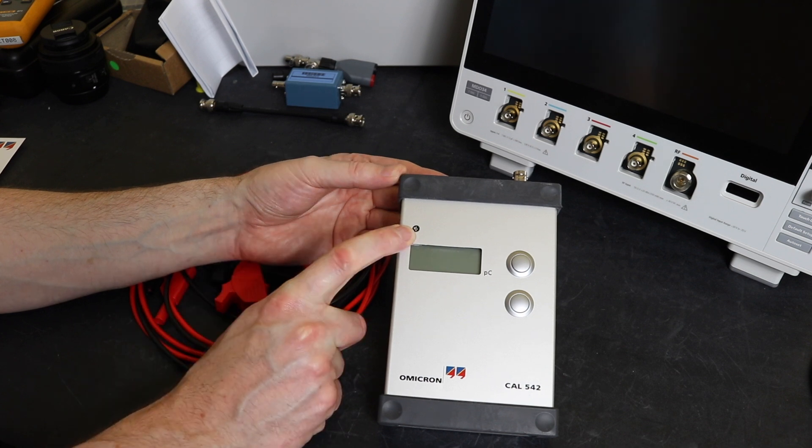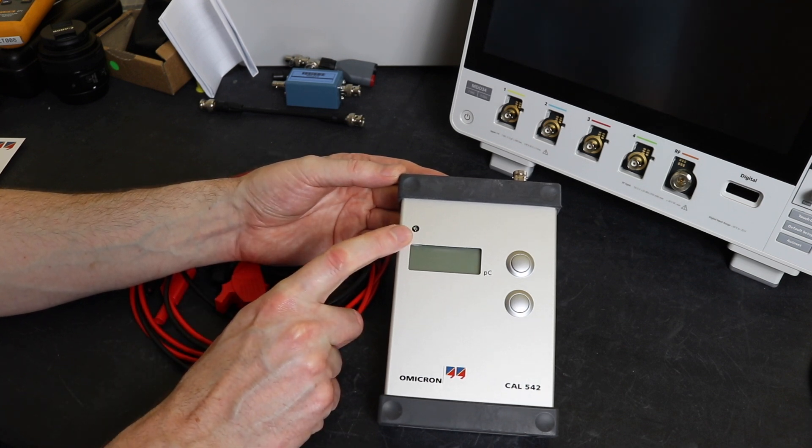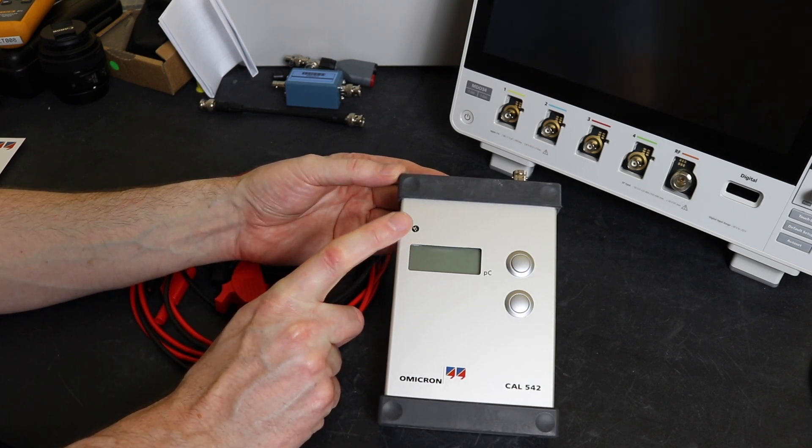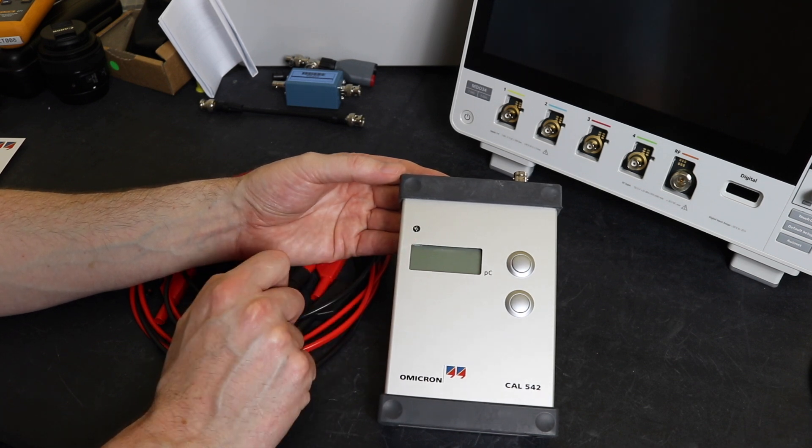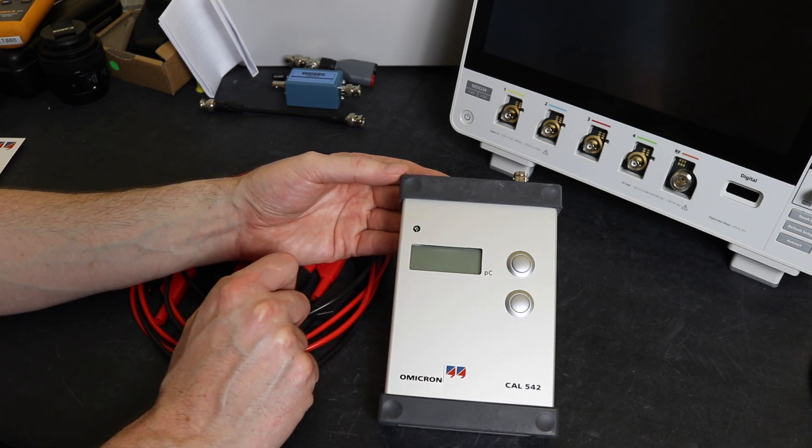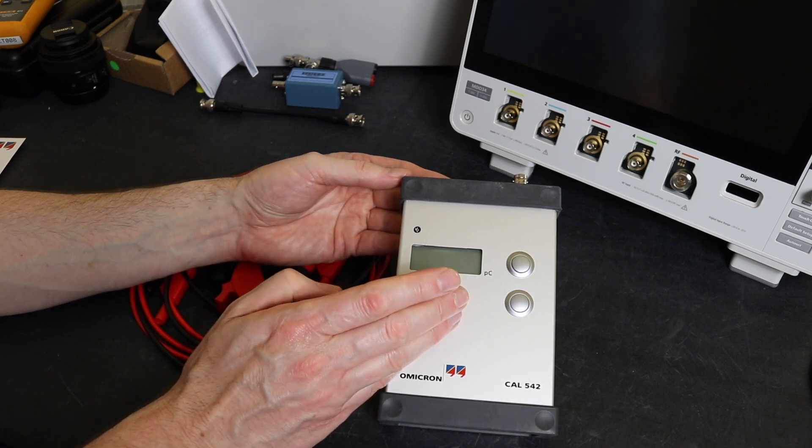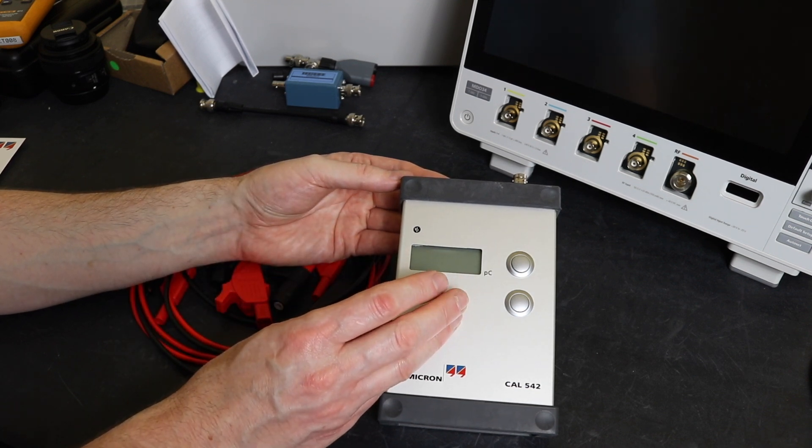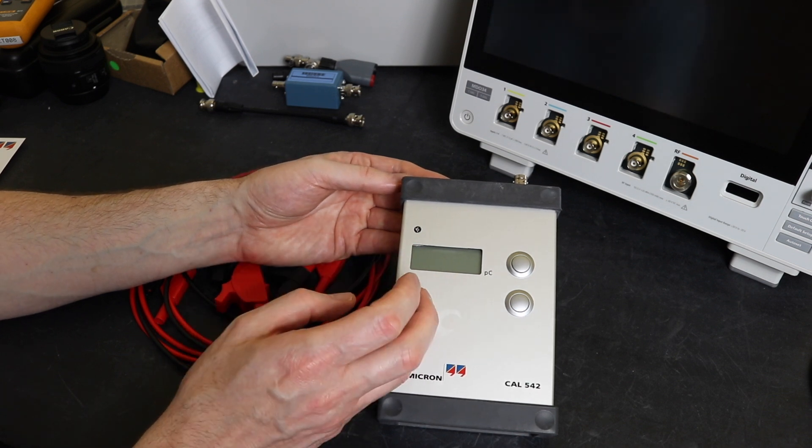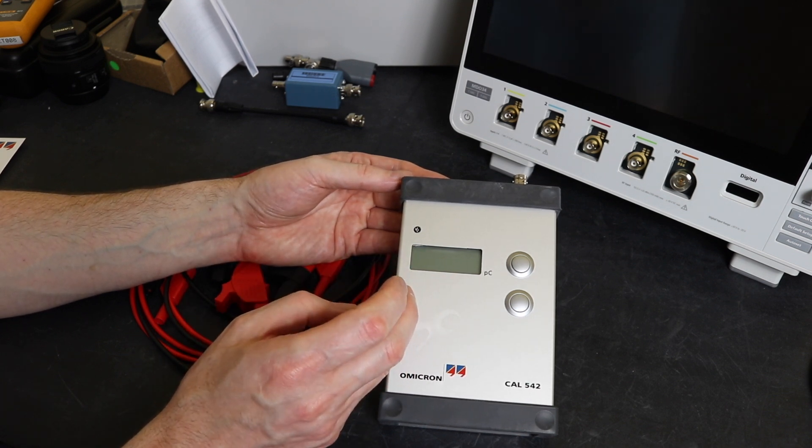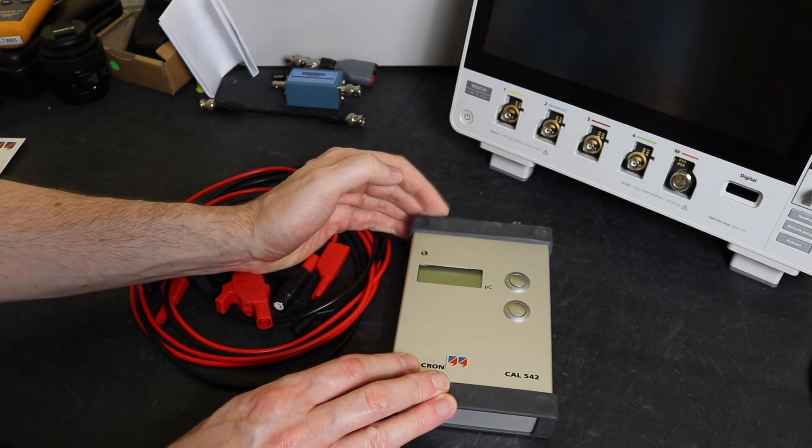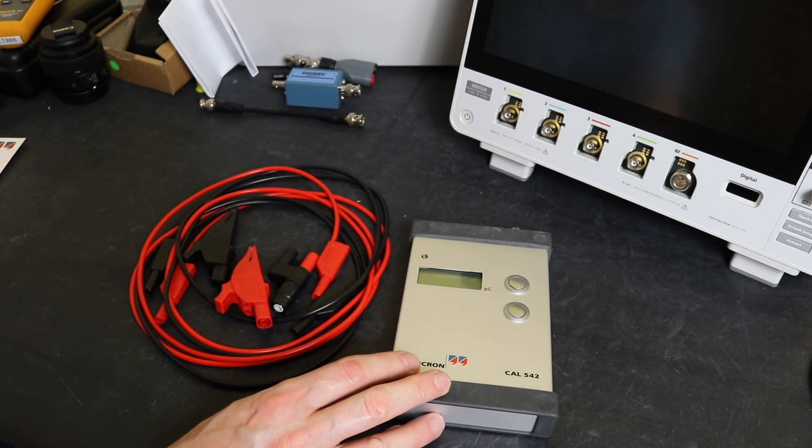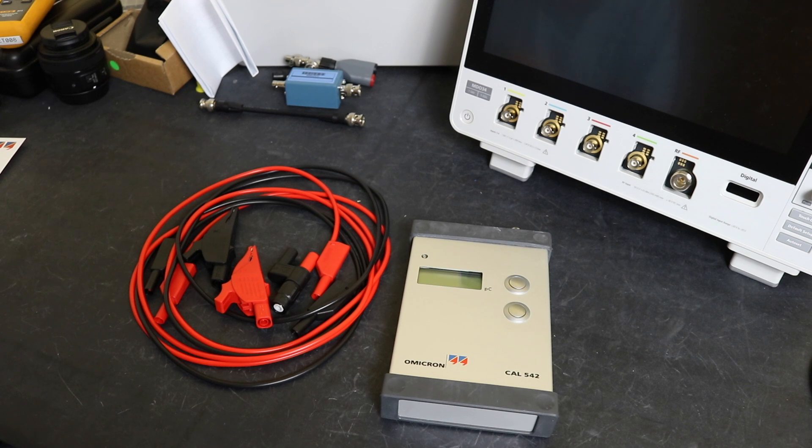There's a little sensor up here as well for light sensing so it synchronizes itself to the mains that you are operating from at the location you're operating at. What this unit does is it allows you to calibrate a machine for partial discharge measurements. When you make partial discharge measurements on an electrical apparatus you can either collect it in millivolt or in picocoulomb which is referred to as apparent charge in the IEC60270 standard.